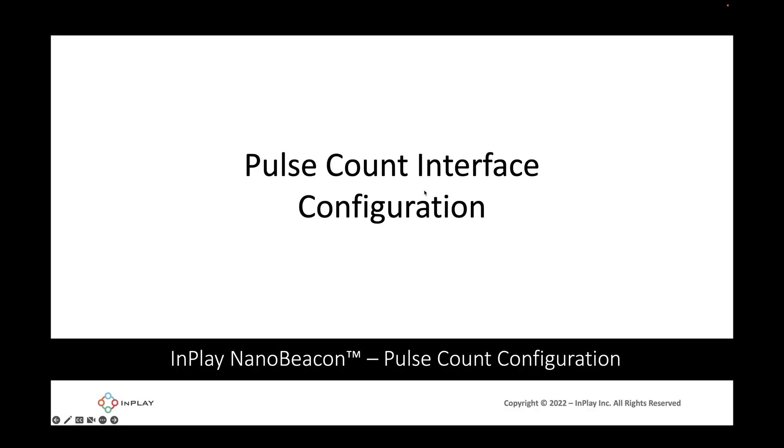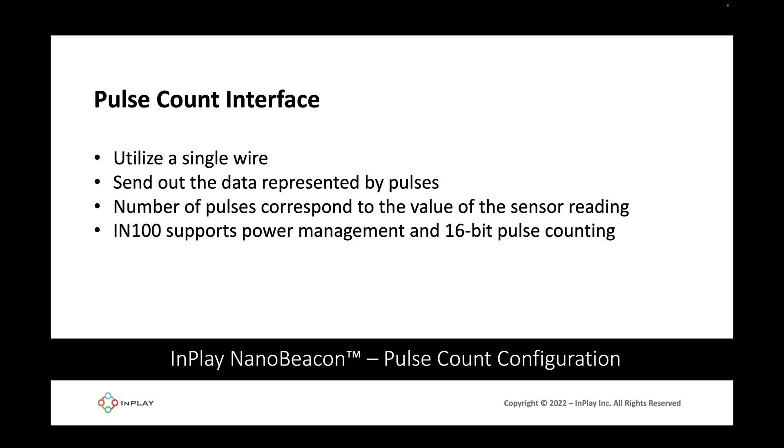Let's learn about the pulse count interface and how we can configure the IN100 to interface with a supported sensor. The pulse count interface utilizes a single wire or a single pin and sends out the data represented by pulses. The number of pulses that are sent out by the sensor will correspond to the value of the sensor reading from that sensor.